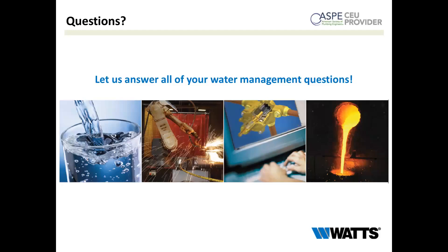Why are fire sprinkler systems unmetered? Fire sprinkler systems are unmetered because you shouldn't pay to put out a fire — it's a greater good. Also, a water meter is one more thing obstructing flow between the water main and the sprinkler head. We want as few obstructions as possible for effective firefighting. That's why they're unmetered connections, which is why they have bypass meters just to detect if there's flow when there shouldn't be. For other uses of fire hydrants, such as construction sites, a backflow preventer is required.